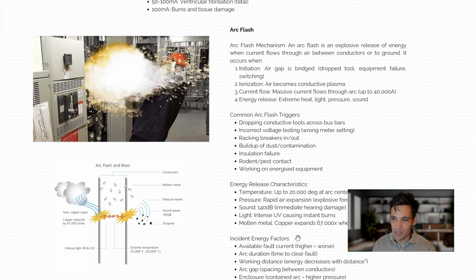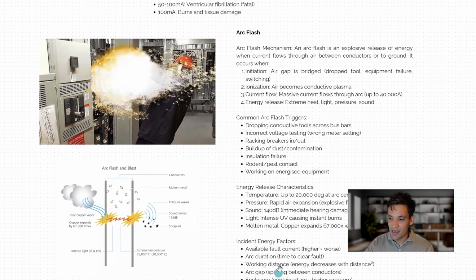But in an industrial facility where you have a 4,000 amp switchboard, you can get huge arc faults even on low voltage equipment. The arc duration, so the longer it takes to clear the fault, the longer it takes the circuit breaker to operate, will make the arc fault worse. The working distance, so how close you are to the actual explosion, the closer you are, much worse. Further away, it's obviously better. The gap between the conductors, and also whether the arc occurs in an enclosed environment.